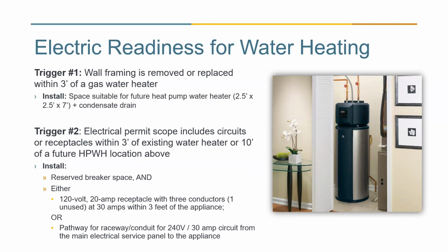And in that case, in addition to the reserved breaker space and the receptacle or conduit, you would need to make sure that there was suitable space for a future heat pump water heater, including a condensate drain, which would be required for the heat pump water heater.